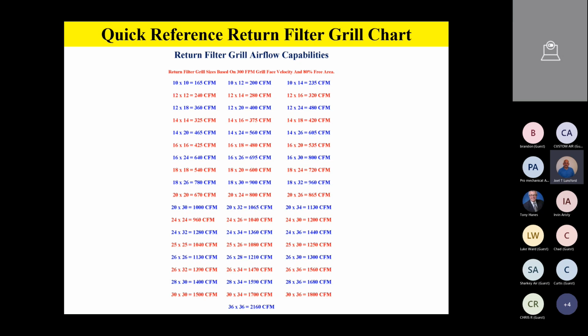Let's do another one. Let's do one that isn't quite so obvious as 1 square foot. Let's take a 20 by 24. So 20 times 24 equals 480 square inches. We then divide 480 square inches by 144 to get square feet, because you always got to get square feet, right? And that gives us 3.33 square feet times 300 feet a minute face velocity, equals 1,000 in this example. So that's how we did it.